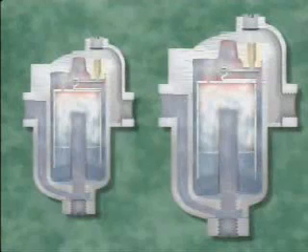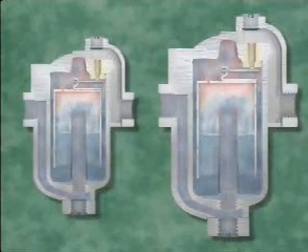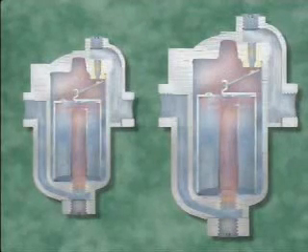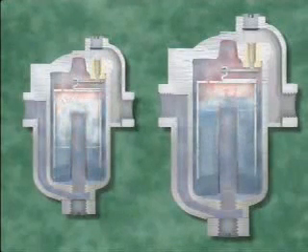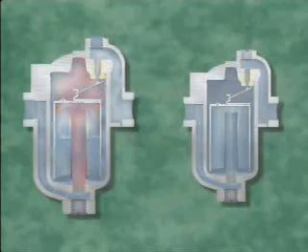If you must replace an old or damaged trap with a completely new one, be sure that the new trap is the right size for the installation. A trap that's too large remains closed for the same amount of time as a properly sized trap, because closing time is based on the rate of condensate accumulation. However, an oversized trap can discharge condensate faster, so it opens for a shorter length of time, causing it to open and close more frequently and consequently wear out faster than a properly sized one. On the other hand, a trap that's too small won't be able to handle all the condensate that's formed, which could lead to water hammer in the drip lines or in the steam system being drained.